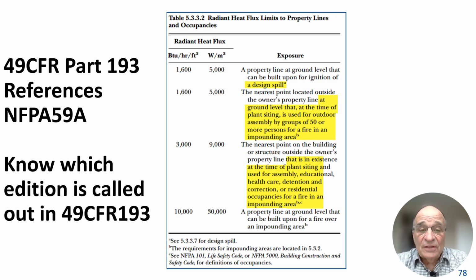This is a part in NFPA 59A. Let's read it. And I'm going to be using the English units. It says a property line at ground level that can be built upon for ignition of a design spill. And it's important that we talk about what a design spill is. What it's saying is that when you build a plant, you cannot have more than 1,600 BTU per hour per square foot at a property line at ground level that can be built upon for ignition of a design spill. Let's say at your property line starts a lake. Well, at the property line starts a lake that cannot be built upon, and you'd have to have really a legal designation as to what you consider what can be built upon. But this is a requirement: radiant heat flux limits to property lines and occupancies.